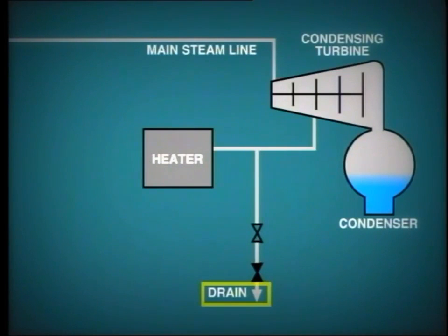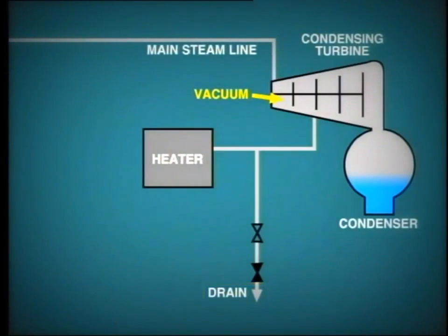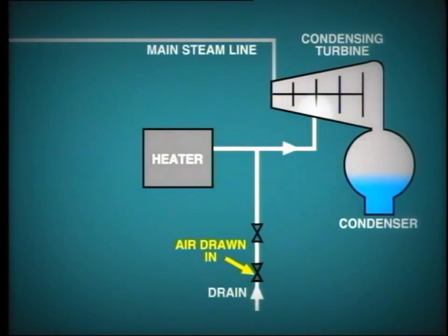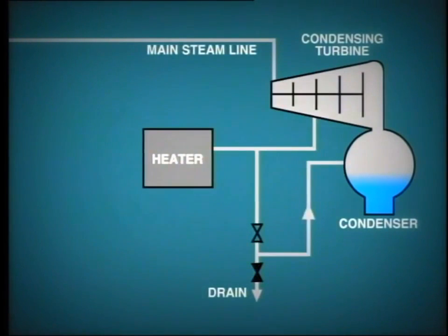But where can these extraction lines drain to? Well, remember during start-up all of the turbine and extraction pipework is under vacuum conditions. So it is obvious that the drains cannot be opened to atmosphere, otherwise we would be drawing air in instead of blowing condensate out. Instead, these drains are discharged to the shell side of the condenser, which of course is also under vacuum.